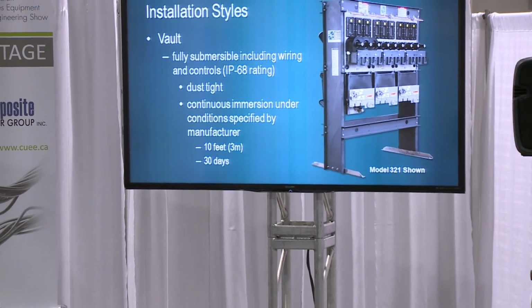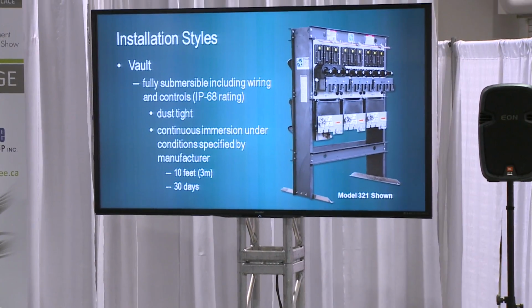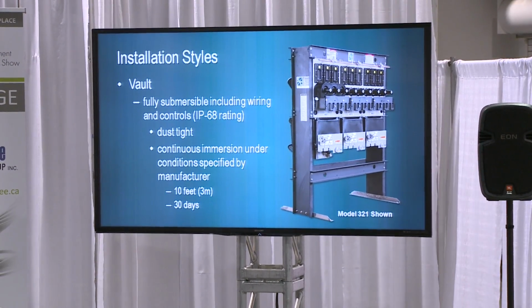Okay. So this is what it looks like. There are 2 different installation styles. This is the vault style. You can see that it's fully submersible. We're going to give it an IP68 rating. The 6 means it's dust tight, and the 8 means that it is watertight to a time and a depth as determined by the manufacturer. In our case, we've chosen 10 feet for 30 days. So our definition of IP68 is shown here.